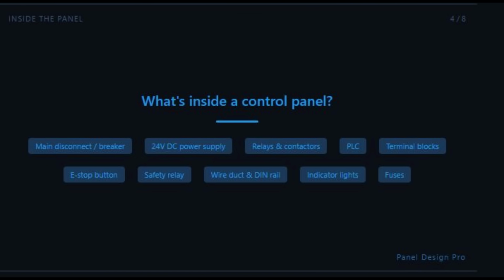Starting at the top, incoming power enters through a main disconnect or circuit breaker. This is the master shutoff. If anything goes wrong, this is what kills power to the entire panel. Next, you'll typically find a power supply, usually converting AC power from the wall into DC power for the control components. Most control circuits run on 24 volts DC.